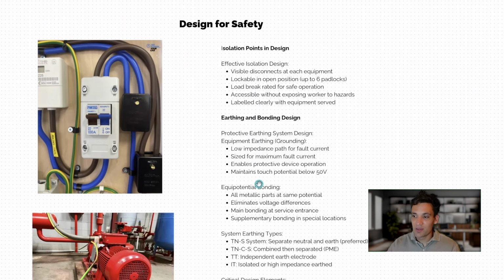The load breaks should be sized for correct, safe operation. So if you're sizing a circuit breaker, it should be able to interrupt current at the safe operating voltage. It should be accessible. Operating those switches should be accessible without exposing someone to hazards. And then everything needs to be labeled crystal clear, and the labeling needs to match exactly what's on the drawings. Second part of electrical safety and design is the earthing and bonding design. And that is basically having an earthing system where there's always a low impedance path designed for the fault currents of the system, and it enables protective devices to operate.